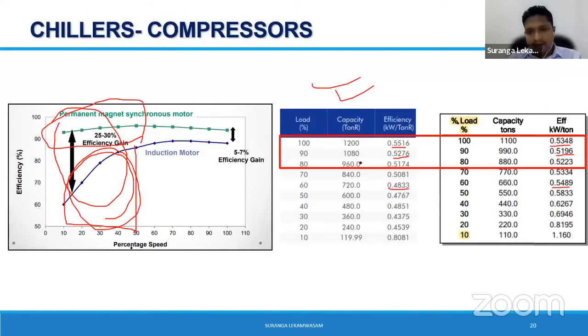Therefore, if you study the profile and efficiency curves of the two chillers, I would recommend that if you have a varying load in your building, there is no better choice than magnetic bearing chillers, because they are very efficient at part loads. So you get the benefit.